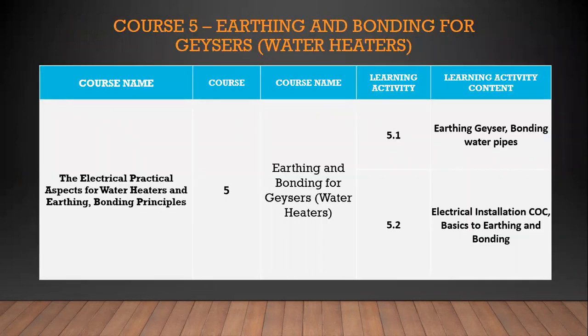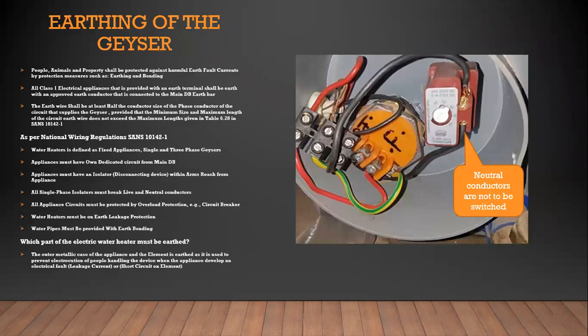Course 5 is the crux of the whole course, earthing and bonding for water heaters. We've addressed the earthing, geyser, bonding, water pipes, and then the electrical installation COC. Just to show you once again in a little bit more detail what we've discussed before of the COC, the regulations, we're actually looking at the COC, just for you to understand it a bit better. We're looking at the earthing of the geyser, your normal earthing. On the picture there, all class 1 appliances are provided with earth terminals.